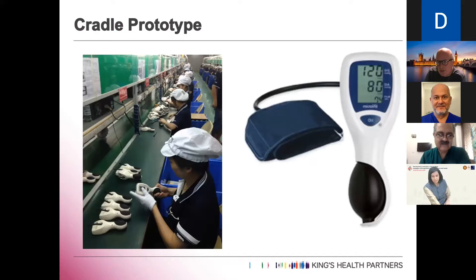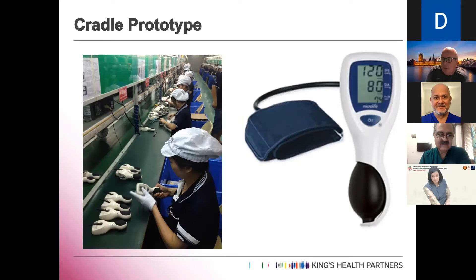The cradle device: the first thing is how do you go about it? First, you get funding. I applied to the Gates Foundation for a small entry-level grant to try out this device. We designed it and linked with a commercial partner who agreed to do this at cost. Here they are coming off the conveyor belts in China — I went to see the factories. The key thing was ensuring quality. I liked this company because they had an algorithm in their blood pressure device suited to pregnancy, and they worked with me to tweak and change it to make sure it was appropriate.